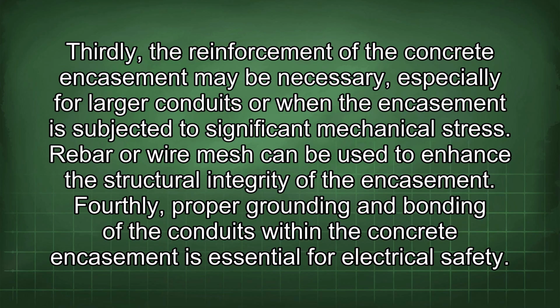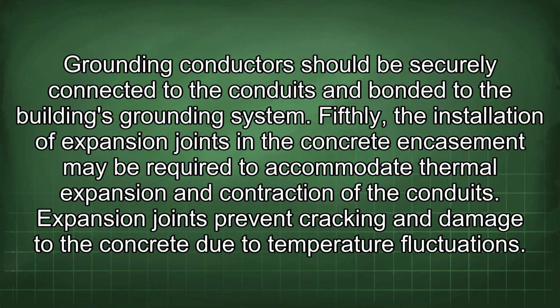Thirdly, the reinforcement of the concrete encasement may be necessary, especially for larger conduits or when the encasement is subjected to significant mechanical stress. Rebar or wire mesh can be used to enhance the structural integrity of the encasement. Fourthly, proper grounding and bonding of the conduits within the concrete encasement is essential for electrical safety. Grounding conductors should be securely connected to the conduits and bonded to the building's grounding system.